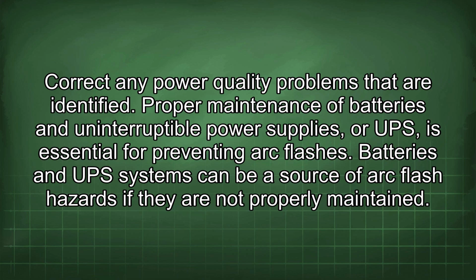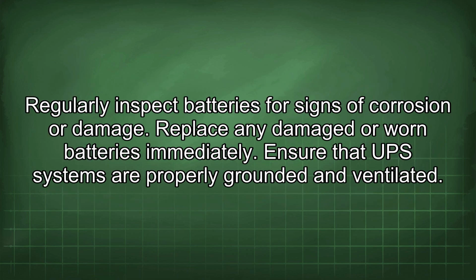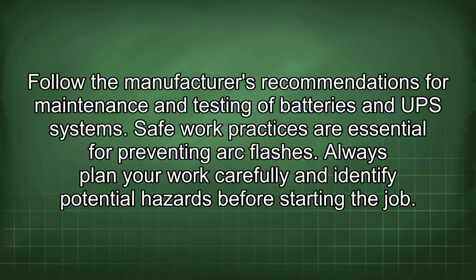Proper maintenance of batteries and uninterruptible power supplies, or UPS, is essential for preventing arc flashes. Batteries and UPS systems can be a source of arc flash hazards if they are not properly maintained. Regularly inspect batteries for signs of corrosion or damage. Replace any damaged or worn batteries immediately. Ensure that UPS systems are properly grounded and ventilated. Follow the manufacturer's recommendations for maintenance and testing of batteries and UPS systems.